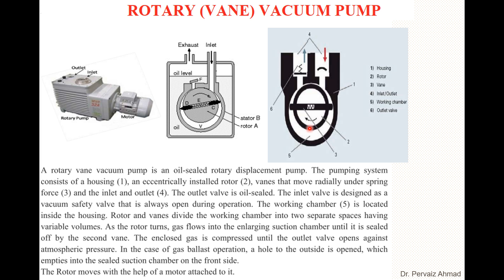This is the working chamber, located inside the housing. As the rotor turns, gas molecules flow into the enlarged suction chamber until it is sealed up by the second vane.